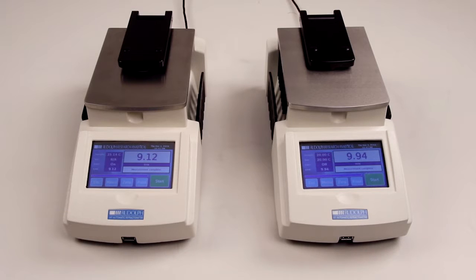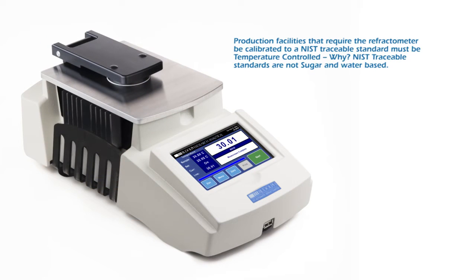Temperature correction is acceptable and accurate for certain samples. Those samples that are primarily sugar and water will measure well with temperature correction only, even when the sample temperature is far from the desired measurement temperature. Samples, including calibration standards that are not sugar and water-based, must be measured using accurate temperature control. Production facilities that require the refractometer be calibrated to a NIST traceable standard must be temperature controlled. Why? NIST traceable standards are not sugar and water-based.